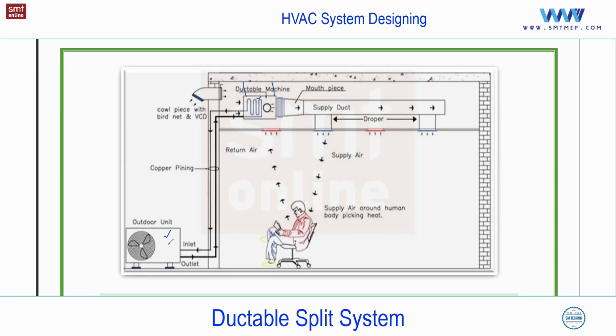And in the outdoor unit, the components are the compressor and condenser, the same cycle. In the indoor unit, you'll find the cooling coil and the blower. Apart from this, you'll find the filter here, and one more pipe for the drain. And again, a drain with a U-trap is required. So the same thing. The new option you see here is that we can attach the duct. And what is a duct? A duct is a sheet metal box which is used to convey the air. In short, we call it an air conveyor. And we have a separate topic for the duct system in part 4. After this we have a separate air system, part 4. In that, we'll discuss this ducting in detail.